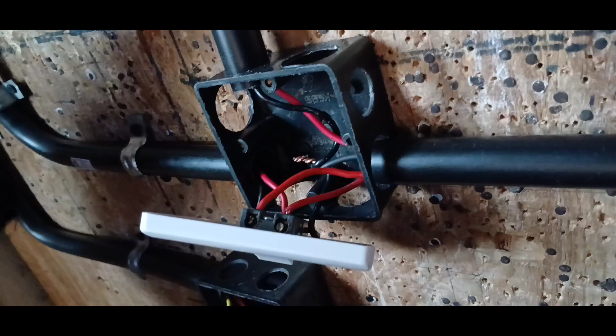Direct. It does not loop anywhere, from the common direct to the bulb. The neutral does not enter this switch. The neutral passes direct to the bulb. As you can see, we have a loop here. The first neutral goes to the bulb. Then here, the neutral does not enter the intermediate switch. It goes straight to the bulb again.